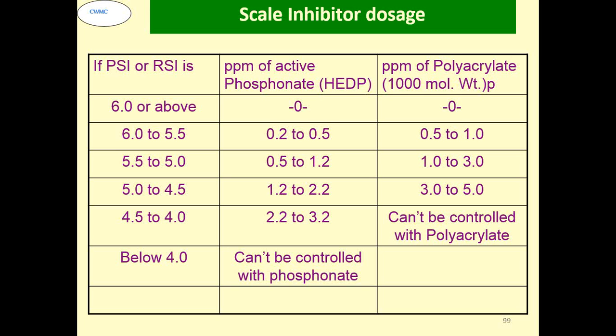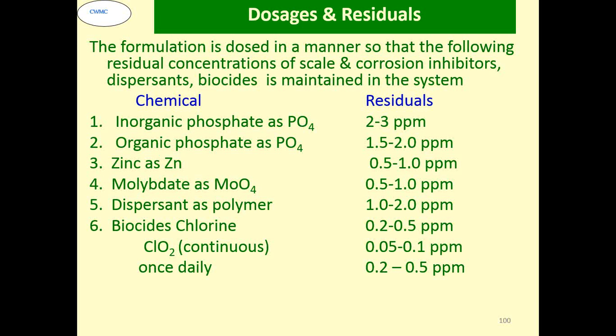Similarly, with the polyacrylate, which is used as a dispersant as well as antiscalant, you can go up to 4.5 to 4. Polyacrylate is not a recommended dispersant or antiscalant below that. Typical residues are seen, but most vendors may not be able to give you the residual level, the active concentration, because of the proprietary nature of the chemicals.